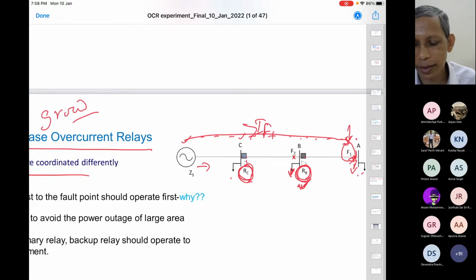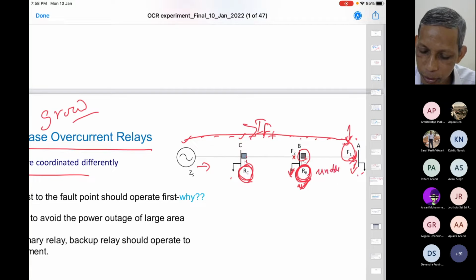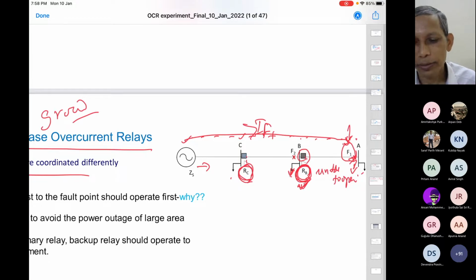So that means the RB should operate there, but how will we achieve that? That is one question. Another question comes here. Suppose there is a possibility that this breaker here is a mechanical switch. With time, it may be unable to open. Then what will happen? This fault will continue, because this is the duty of RB. The fault will continue and continue, so it will go on damaging. It's a problem case, so this is not good to avoid.